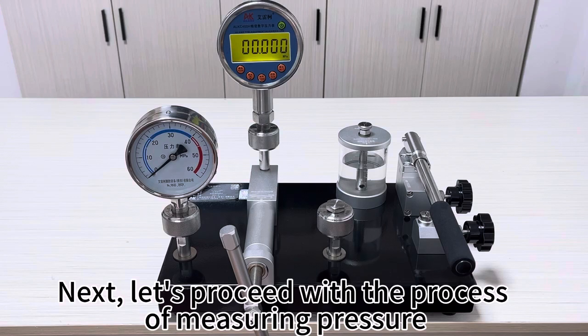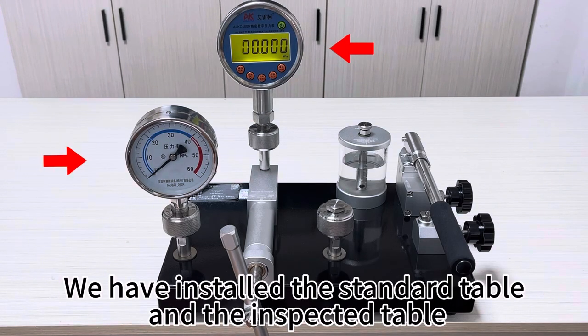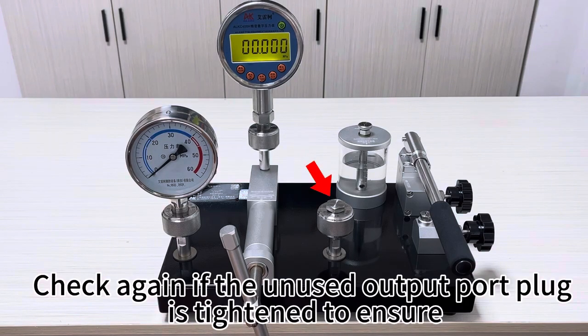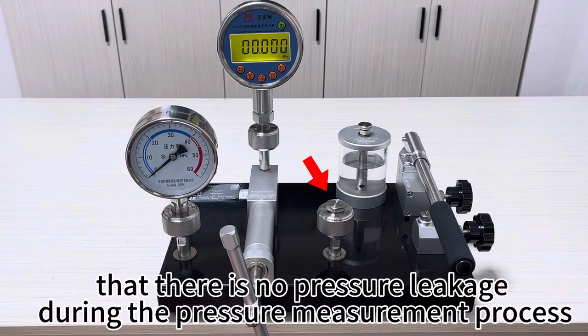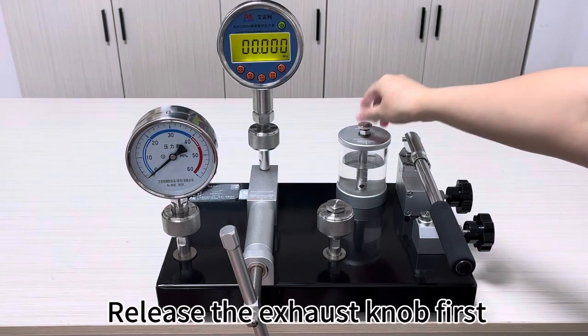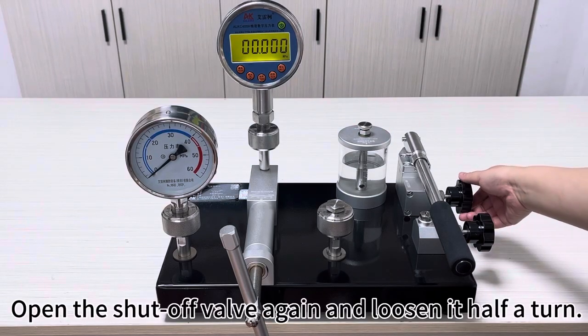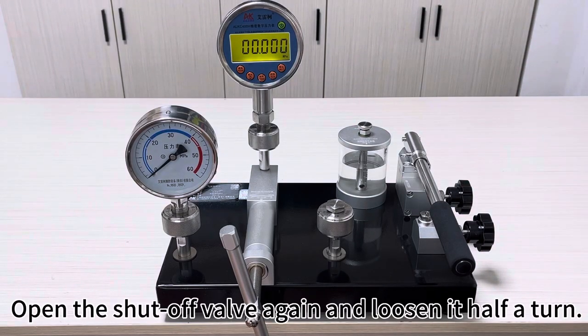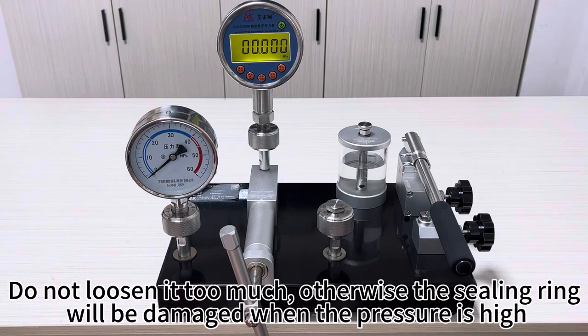Next, let's proceed with the process of measuring pressure. We have installed the standard table and the inspected table. Check again if the unused output port plug is tightened to ensure that there is no pressure leakage during the pressure measurement process. Release the exhaust knob first. Open the shut-off valve and loosen it half a turn. Do not loosen it too much, otherwise the sealing ring will be damaged when the pressure is high.